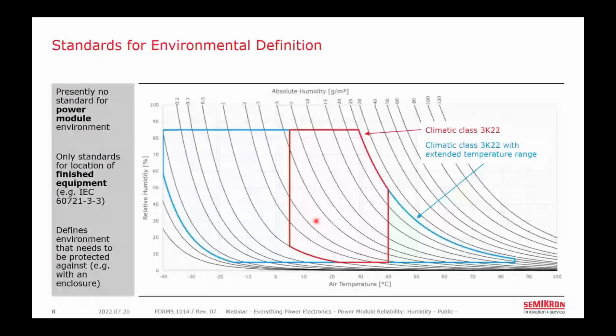And so climatic class 3K22 is actually a relatively benign environment, as this class also states that condensation and wind-driven precipitation are not allowed, which you might see in an indoor industrial environment. There are other climatic classes where condensation is allowed, in which case the electrical enclosure would have to be designed such that the condensation did not affect the electronics inside it.